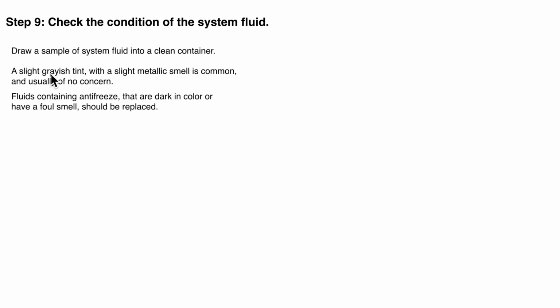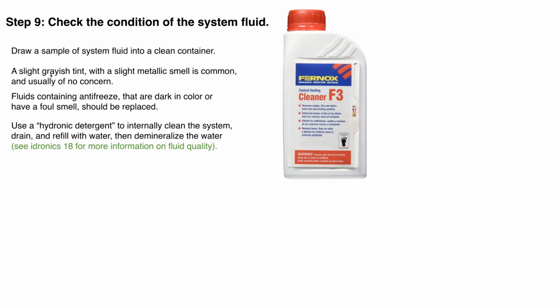If you're smelling something that is foul, if the system has antifreeze in it, that antifreeze is probably degraded thermally, especially solar thermal systems were classic causes of this due to stagnation. That fluid needs to be replaced. So I would recommend that you use a cleaner, and there are other products. There's Fernox, there's Rhomar, there's Sentinel, there's other products to market. I call these hydronic detergents. They go in and basically clean the inside surface of the system.